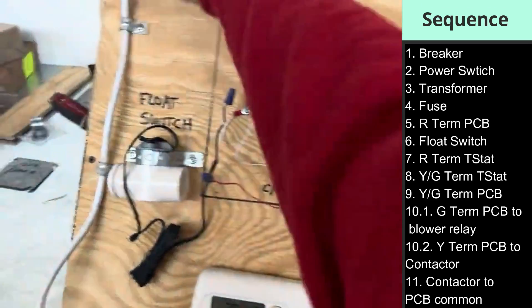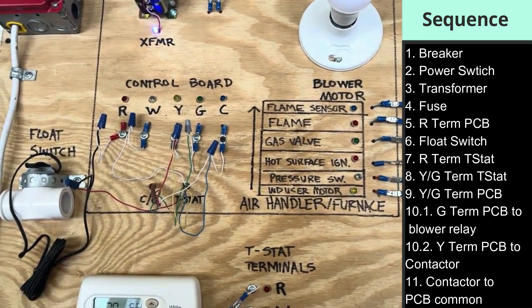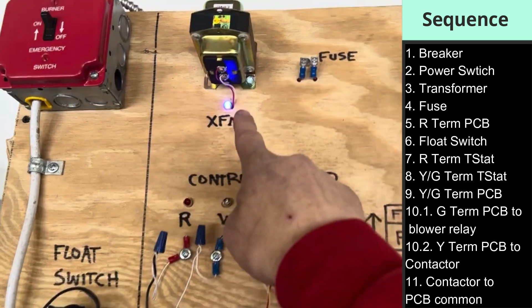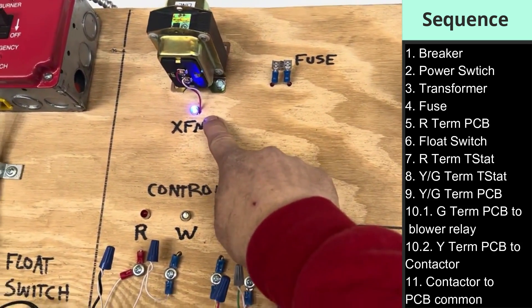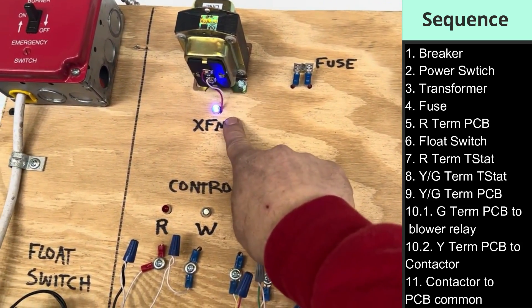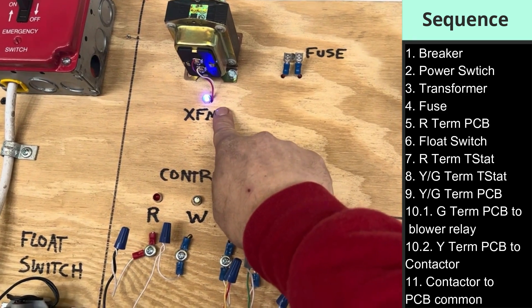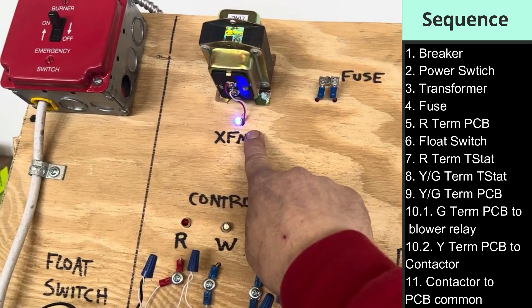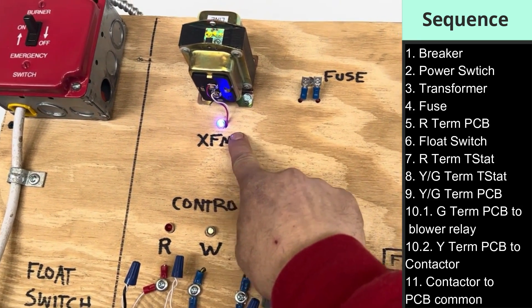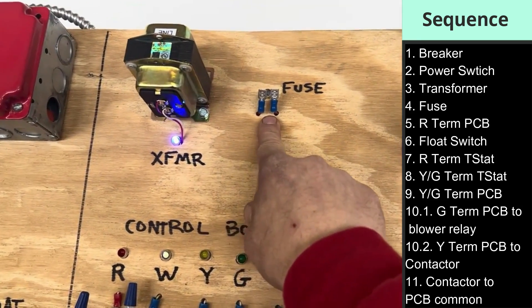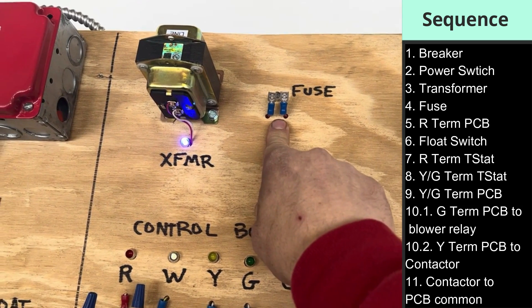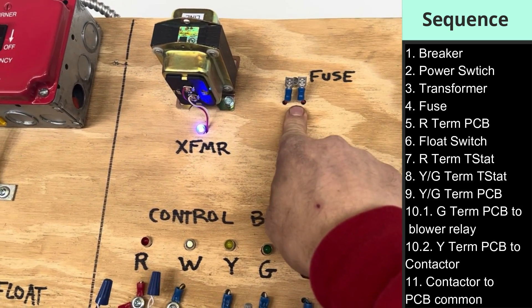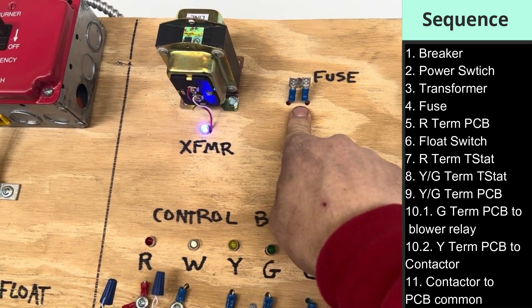The system is off. I'll turn it back on and simulate another problem. You can see nothing's happening at all, but I still have power on the secondary side of the transformer. Looking at our sequence: the breaker is on, the switch is on, the transformer is good, we have 24 volts — where does it go next? To the fuse. I pulled the fuse out to simulate a blown fuse. What that means is we have a short in the system somewhere — now we know what the problem is and just need to find that short.